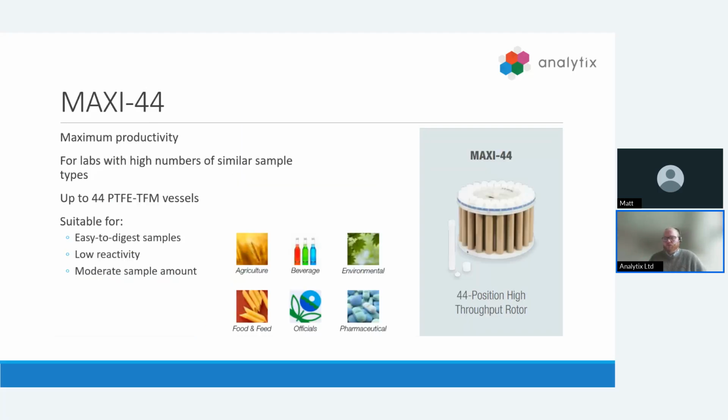So let's go into each of the rotors in a bit more detail. I'll cover these specifically for the ETHOS system, but you have the options for the Lean as well. So we have the Maxi 44 here, which is up to 44 position rotor, which offers maximum productivity for labs processing large sample batches.